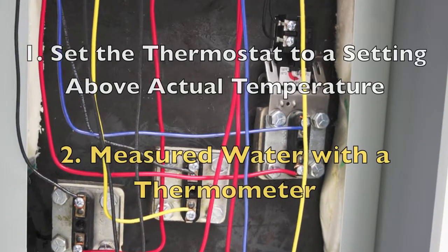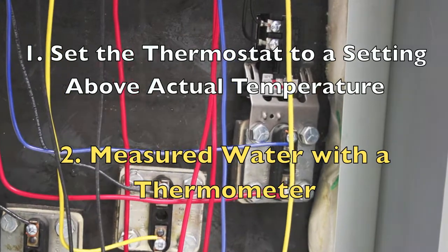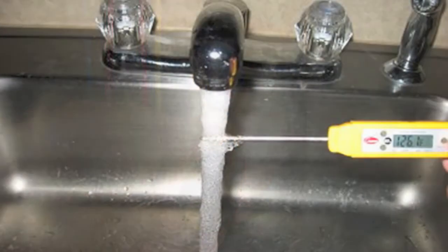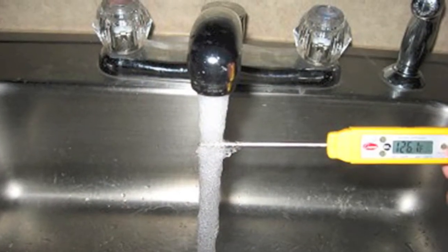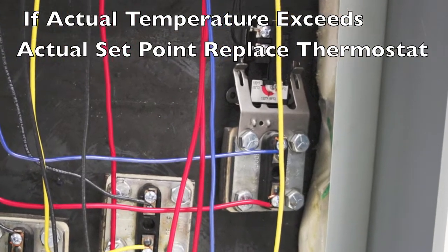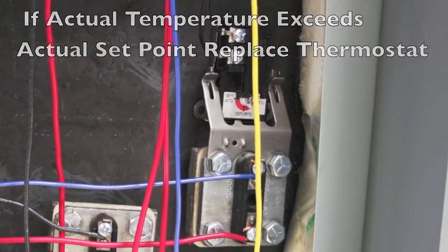To verify the thermostat is operating properly, set the thermostat to a setting above actual temperature. Allow heater to satisfy. A sample taken from the closest tap, measured with a thermometer, should be within the range of the actual setting. If actual temperature exceeds actual set point, replace the thermostat.